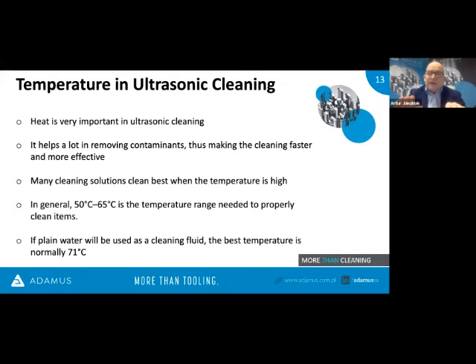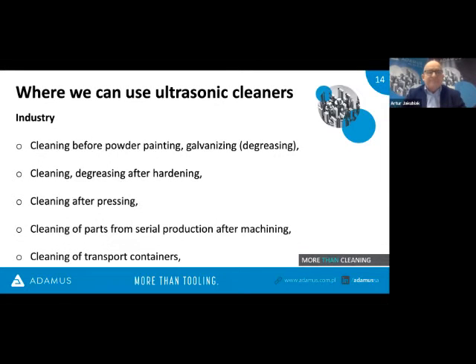Of course, because I said that we are using some detergents, this range of temperatures, 50 to 65, is for the cleaning liquid with the detergent. If we are using plain water, no detergents, we need to increase the temperature a little bit. So normally 71 Celsius is optimum for clean water if we are not using any detergent.